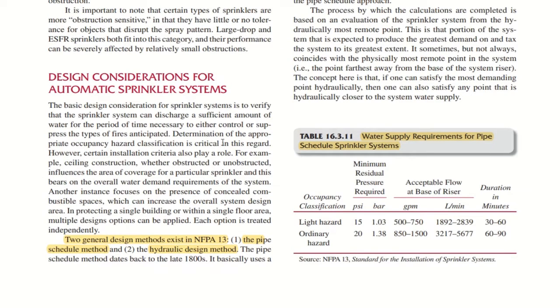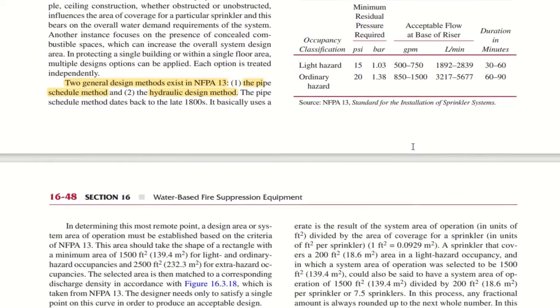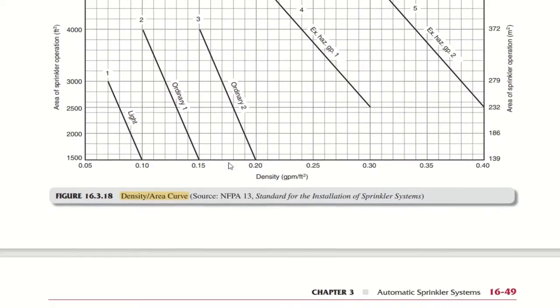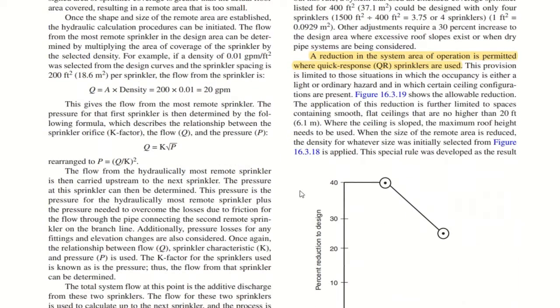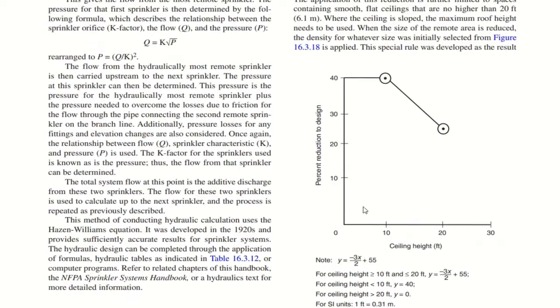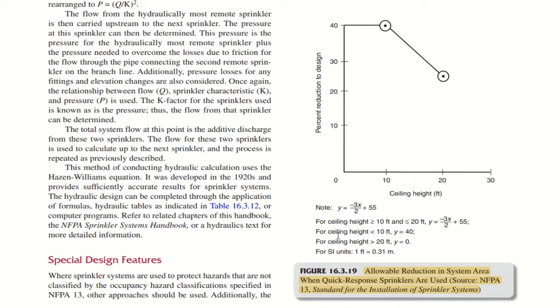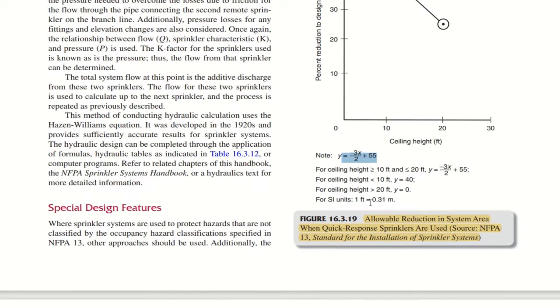Apart from that we have seen there are two different design methods existing in NFPA 13. One is pipe schedule method and the other is hydraulically designed method. We have gone through one table, water supply requirements for pipe schedule sprinkler systems. This is an important table. Apart from that you have density area curves, and we have seen the reduction of area if we are considering the quick response sprinklers. So this is the graph, and this is the curve, and this is the formula you have. Based on this formula we need to calculate the reduction of area while considering the hydraulic calculations.